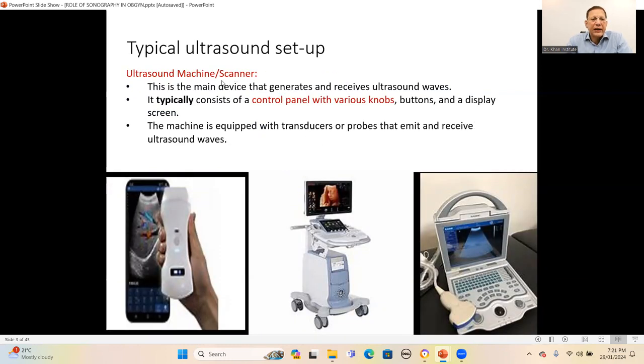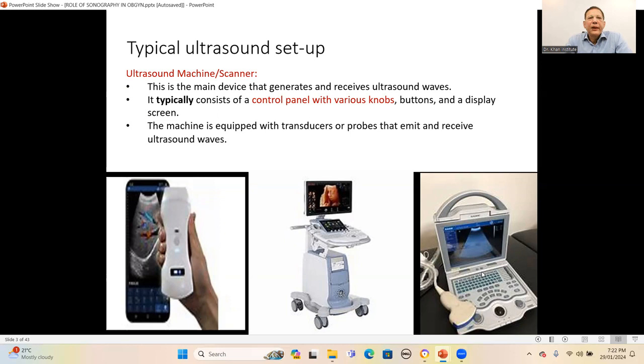The ultrasound machine or scanner typically consists of a control panel provided with various knobs, keys and buttons. These knobs are used for adjusting the parameters and selecting different imaging modes like A mode, B mode, M mode and color Doppler mode. These knobs also provide functions like depth and focusing, overall gain, and time gain compensation, which are all used frequently to optimize the ultrasound image.